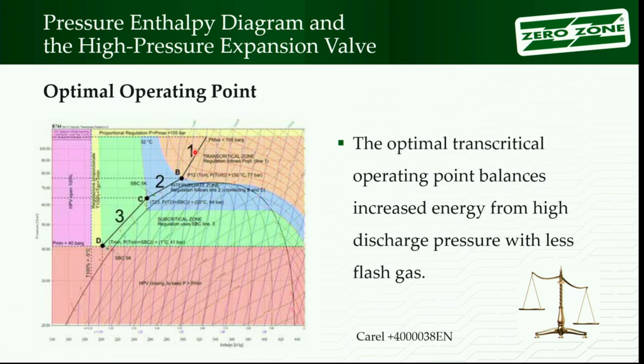And we're going to see in a moment on the next slide, to get more liquid, I have to raise the pressure. If I raise the pressure on a compressor, what happens to the energy? Go up or go down when I raise the discharge pressure? Goes up, right? I'm going to be paying the electric company more on it. What happens to the volumetric efficiency of the compressor? Goes down, right? So it's kind of a double hit. So when I raise up the pressure, it's costing me something. On this side of the balance beam, it's costing me more energy, some losses in capacity.